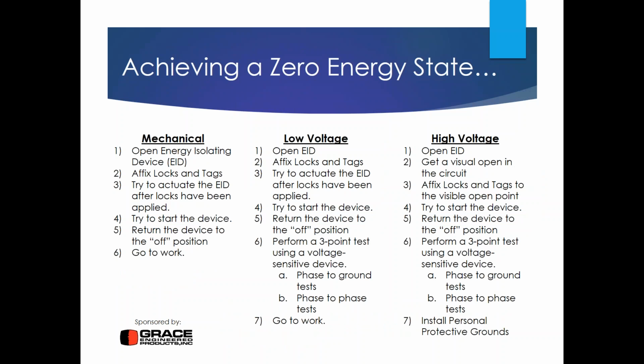Under the left column, we have straight up mechanical lockout tagout. Let me walk you through these steps because they're going to be repeated in the next two systems. For straight mechanical lockout tagout, assuming we've already bled off any stored energy, the first thing we do is open the energy isolating device itself. We affix locks and tags to that device. Step 3 in my outline is an additional step that is not required under OSHA or 70E. It is something I recommend, which is to try to close the device in with the energy isolating device locked out. There's a remote possibility that you'll be able to do that with the locks and tags on there, and it's important that you know that.